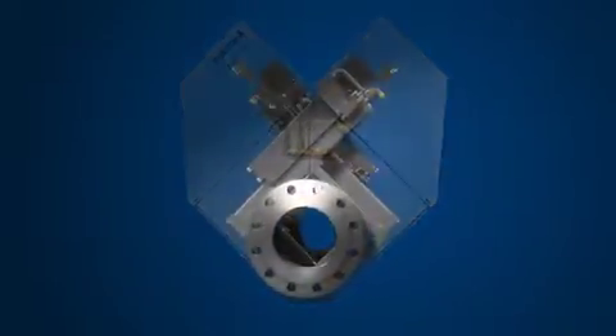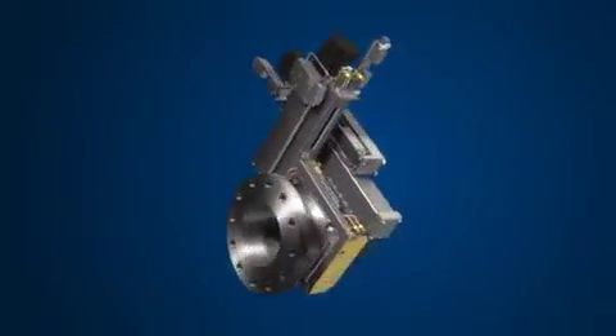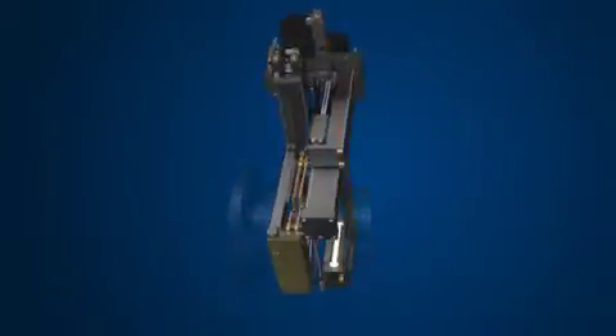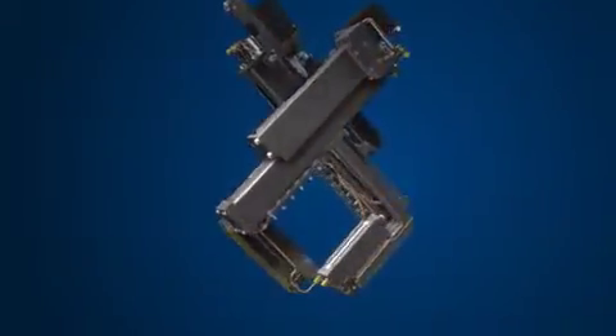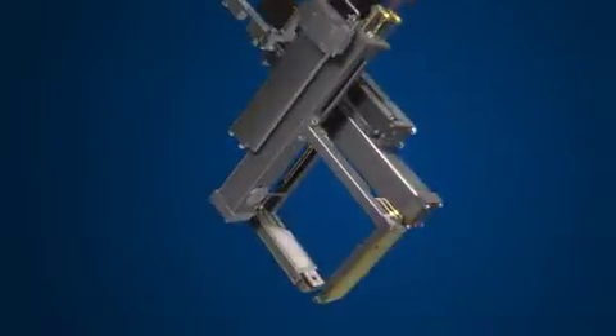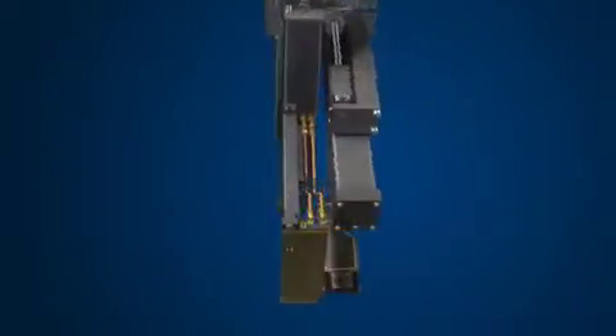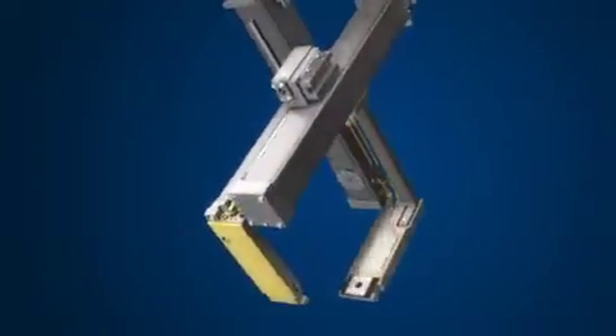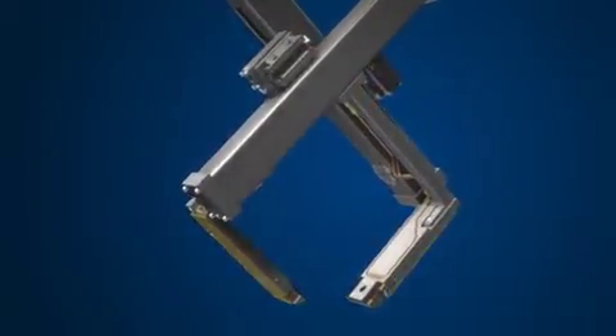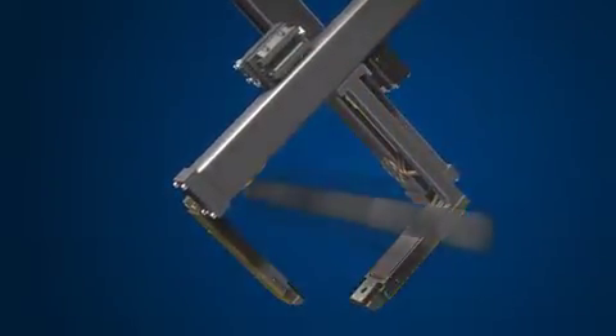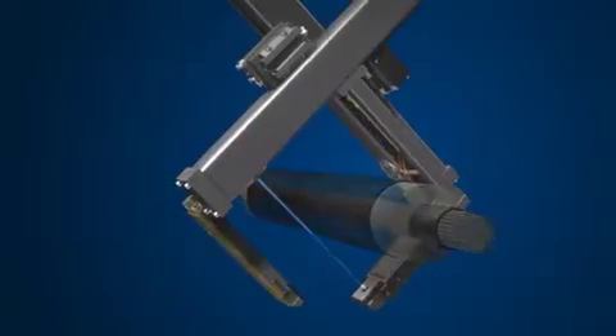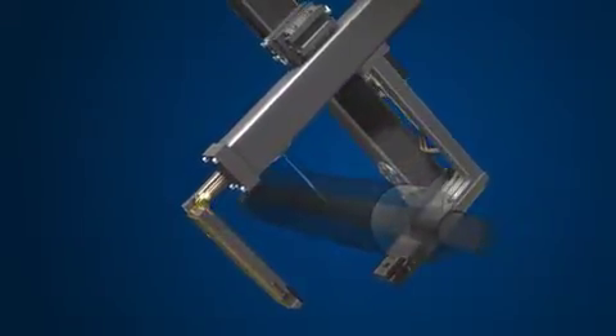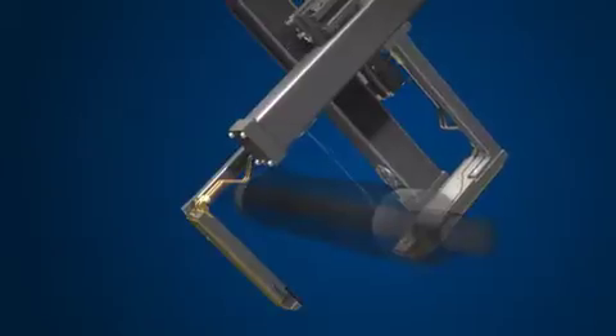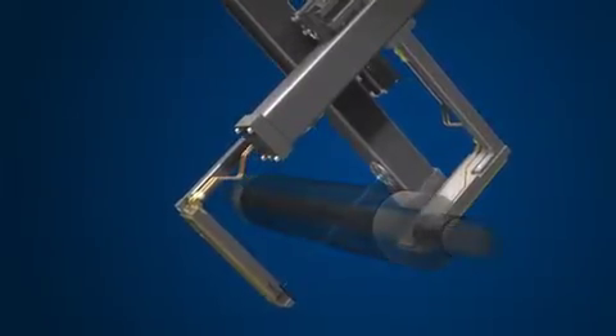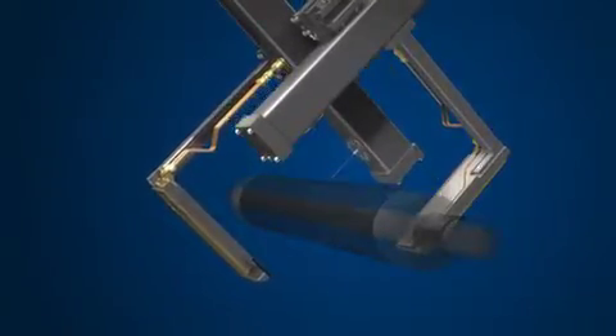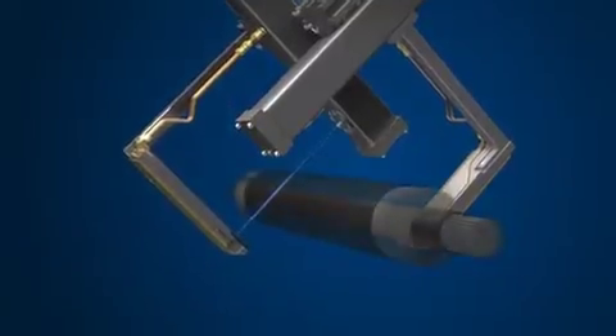The precision and reliability of the X-ray 8000 NXT ensures a high and fast return on investment. Two high-speed scanners scan the product on a non-contact basis with X-rays. The continuous measurement guarantees accurate values. Within seconds, the diameter, ovality, wall thickness, and eccentricity of the cable are calculated with outstanding precision, without any need for calibration procedures.